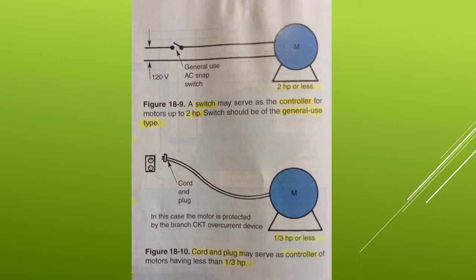The circuit breaker for a branch circuit may serve as a controller. However, the longer delay prior to opening may permit a fault current to damage the controller or the motor. The circuit breaker may also serve as the disconnect. A cord and plug arrangement may serve as a controller for motors at less than 1/3 horsepower. Figure 18-10. The same arrangement may also serve as a disconnect.